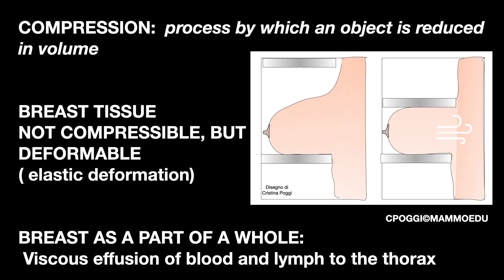Let's start with the definition of compression. It is a process by which an object is reduced in volume. In reality, the breast tissue is not compressible, since its volume does not change. It should be said, more precisely, that it is deformable. The breast shape is changed and then restored once the process is finished — we speak of elastic deformation. However, if we consider the breast as part of a whole, the thorax, then yes, there is a decreasing volume, a very small one, caused by the lowering of the paddle, which causes a viscous effusion of blood and lymph from the breast to the chest.